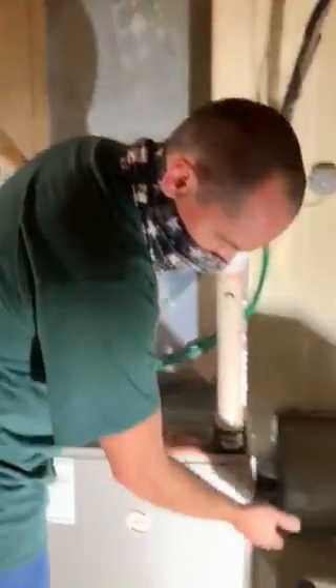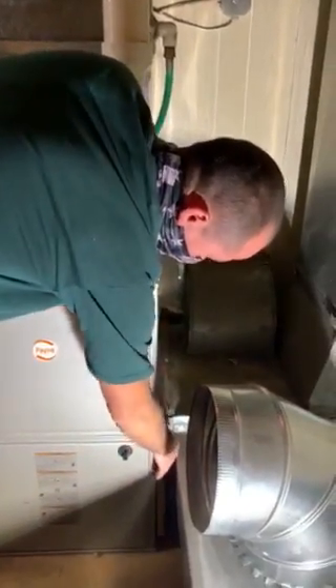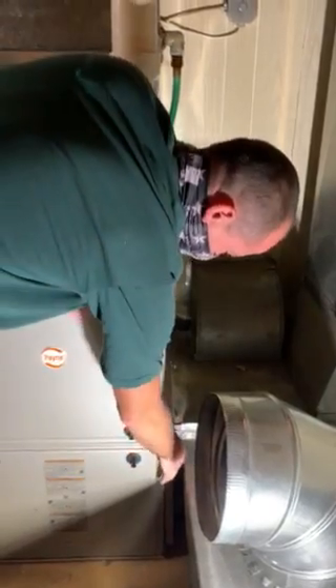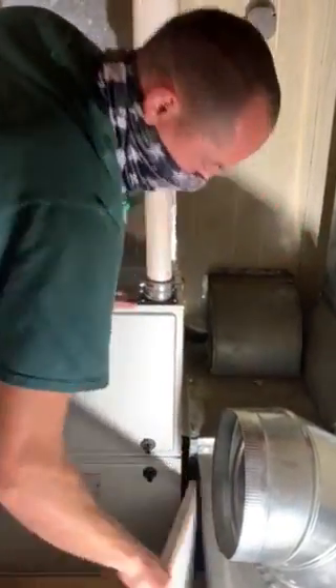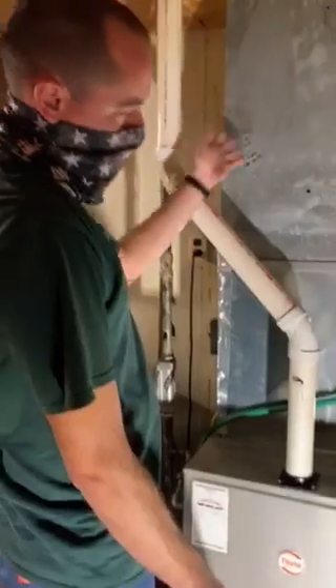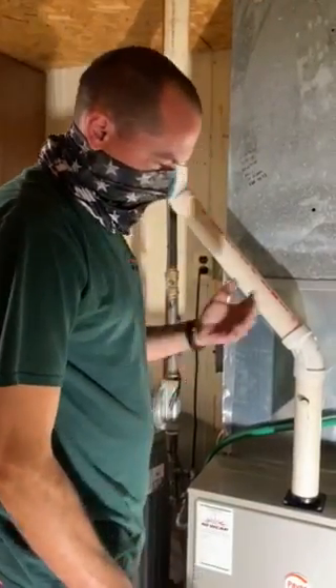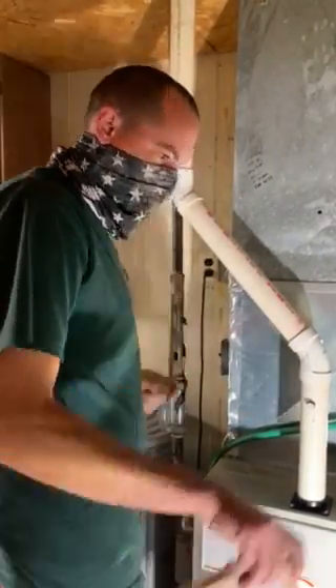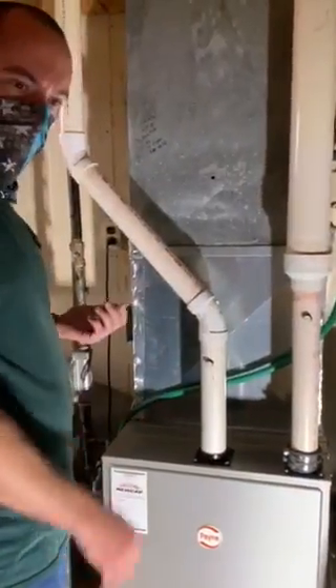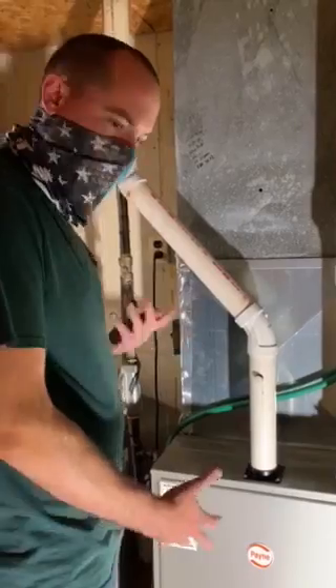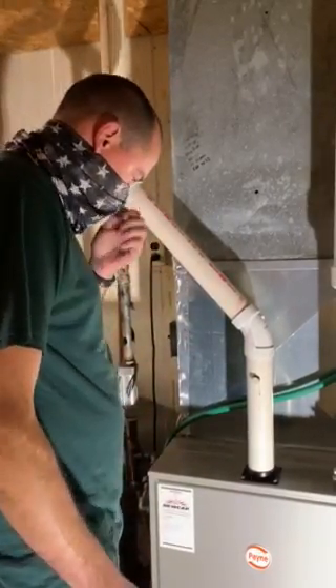Or if the filter is the correct size, it could be too dirty. If it gets too dirty, it'll have the same exact effect. You won't have enough air flowing across your air conditioning coil, and the same with the heat exchanger. Over time, it could cause your heat exchanger to crack or fail prematurely because of the lack of airflow across it.